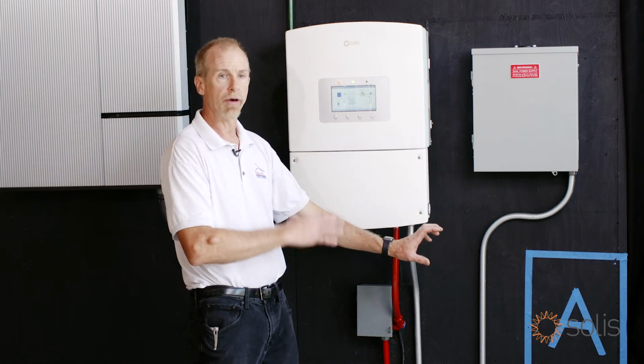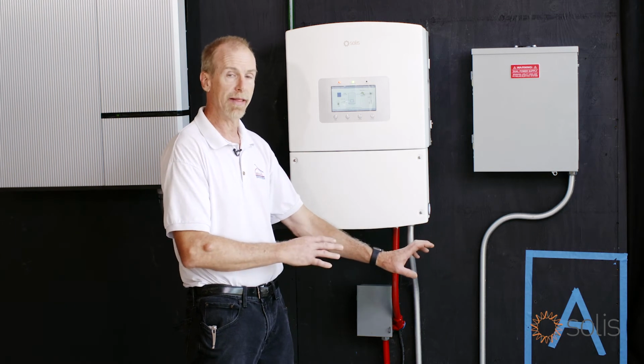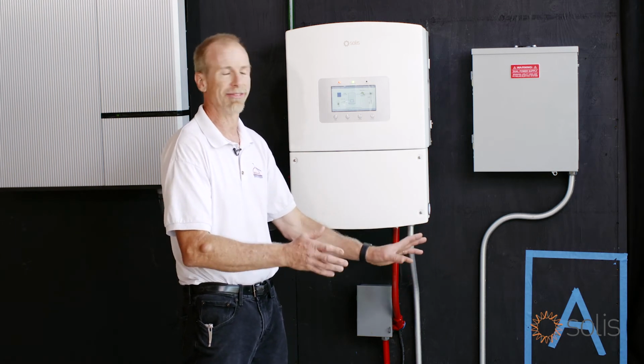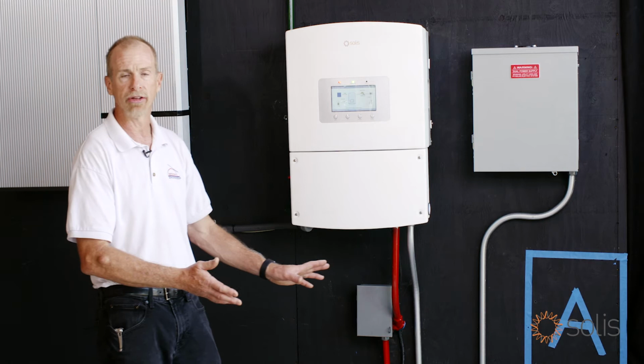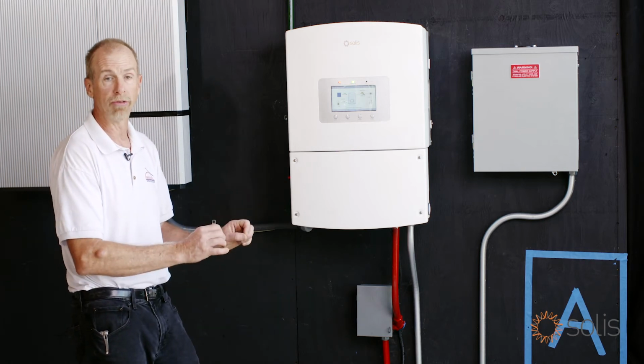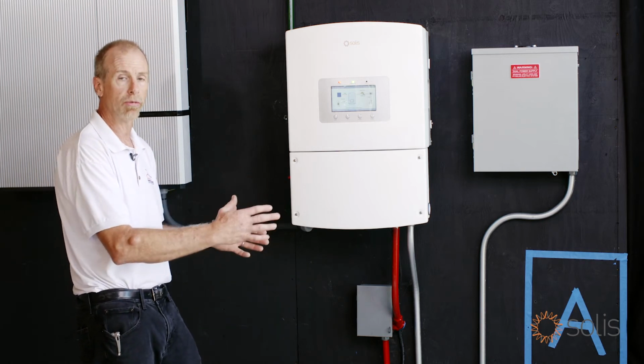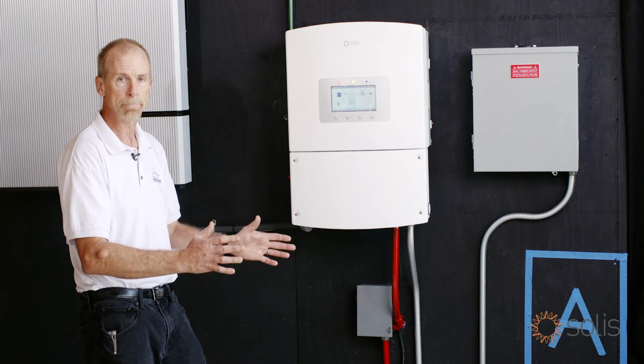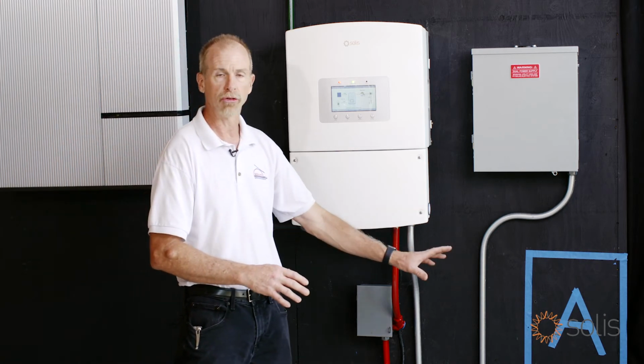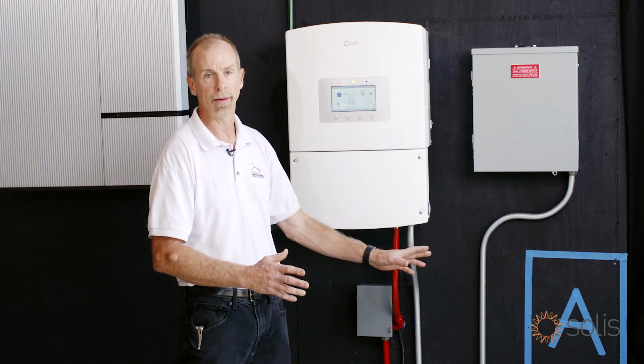And we could have all of our 120 volt loads on one side of that transformer and it would work. Now, it's not practical, nor are we going to set it up that way, but it's capable of doing that. So it's fully capable to the rating of the inverter, which is great. We don't have to worry about the auto transformer limiting us in any way. So let's review mounting the auto transformer.